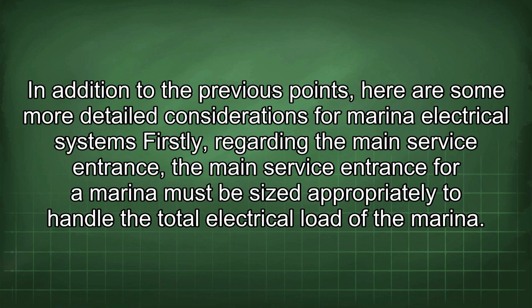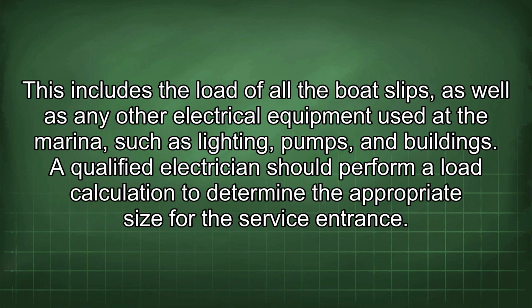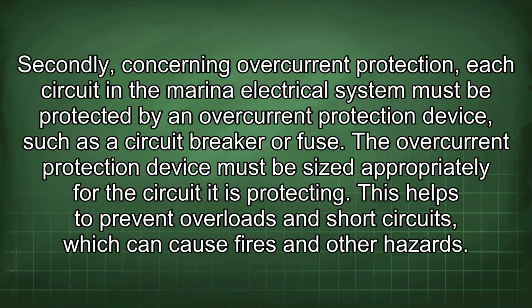The main service entrance for a marina must be sized appropriately to handle the total electrical load of the marina. This includes the load of all the boat slips, as well as any other electrical equipment used at the marina, such as lighting, pumps, and buildings. A qualified electrician should perform a load calculation to determine the appropriate size for the service entrance. Secondly, concerning overcurrent protection, each circuit in the marina electrical system must be protected by an overcurrent protection device, such as a circuit breaker or fuse. The overcurrent protection device must be sized appropriately for the circuit it is protecting. This helps to prevent overloads and short circuits, which can cause fires and other hazards.